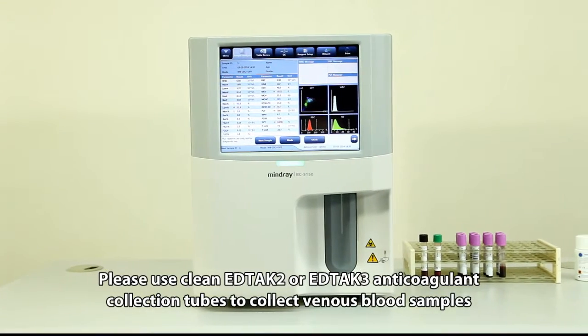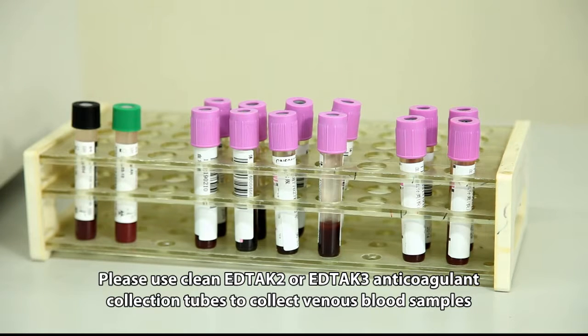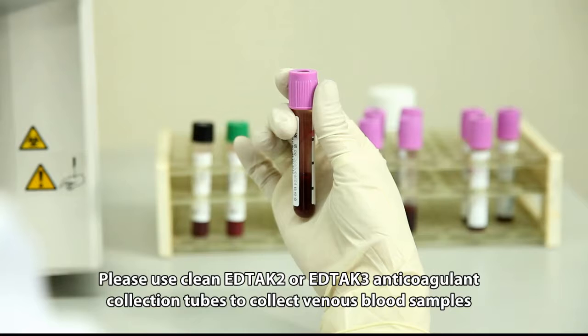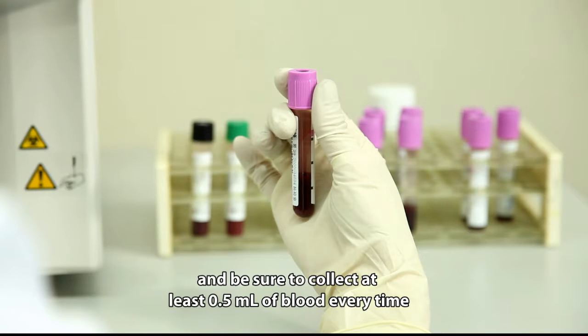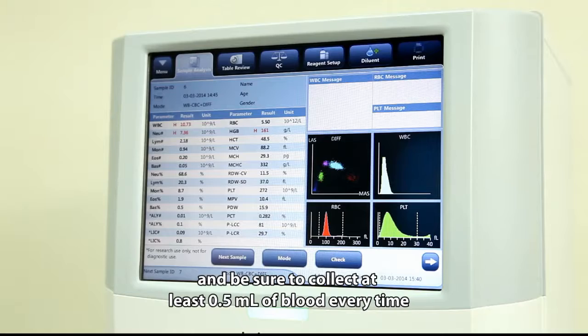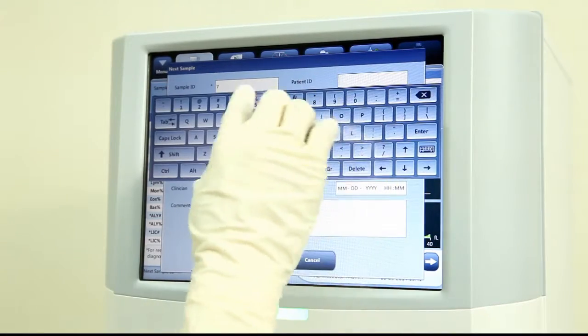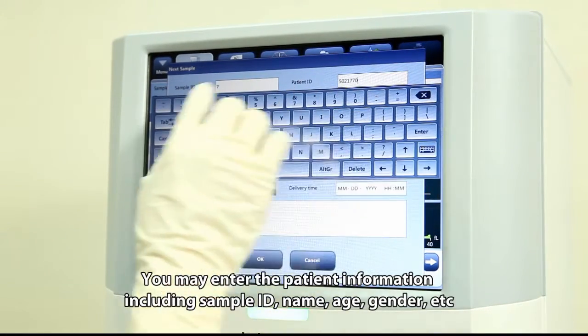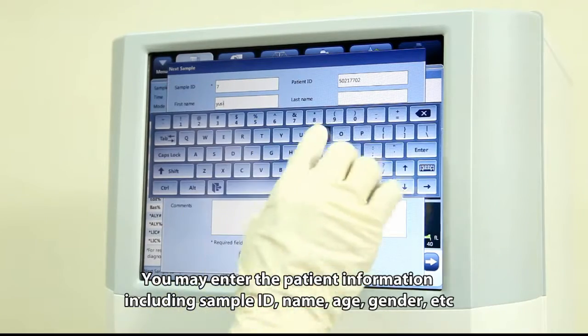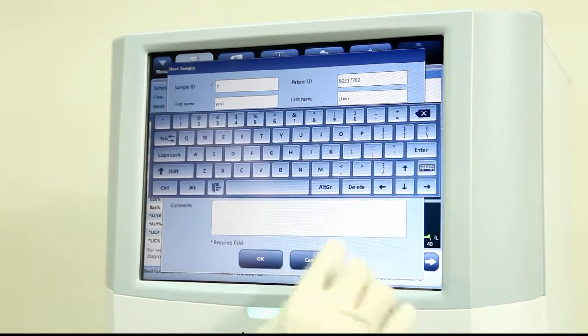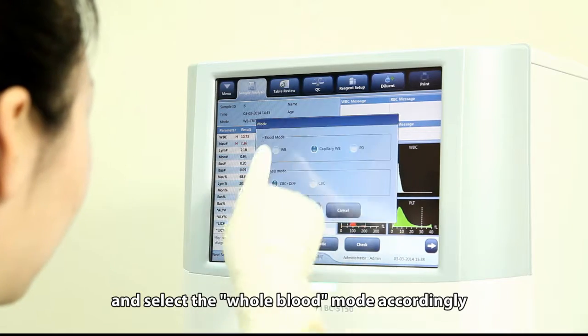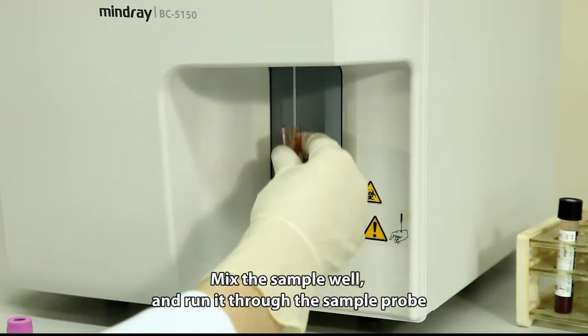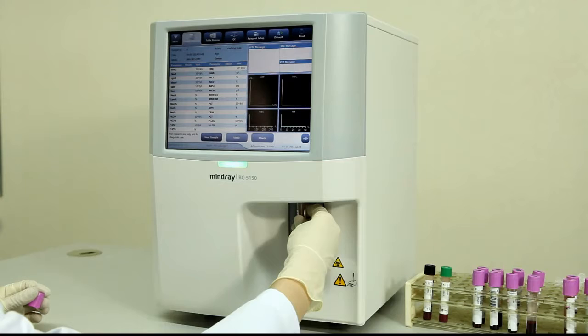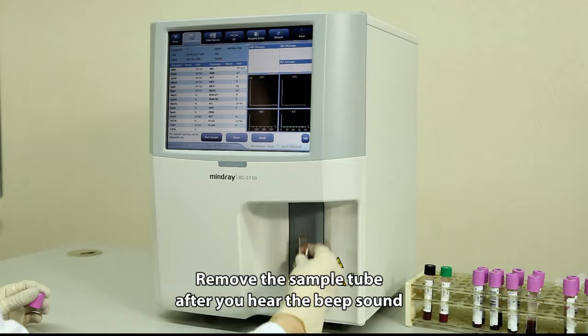Please use clean EDTAK2 or EDTAK3 anticoagulant collection tubes to collect venous blood samples, and be sure to collect at least 0.5 milliliters of blood every time. You may enter the patient information including sample ID, name, age, gender, etc. and select the whole blood mode accordingly. Mix the sample well and run it through the sample probe. Remove the sample tube after you hear the beep sound.